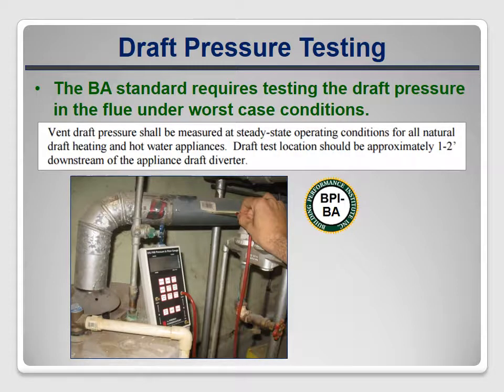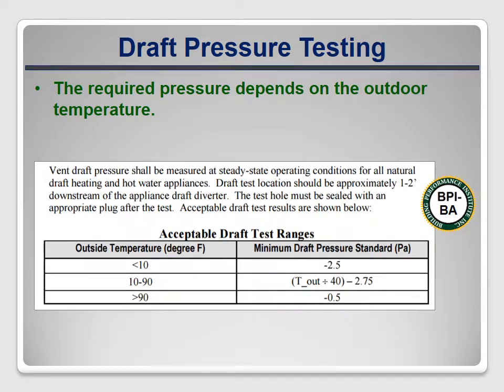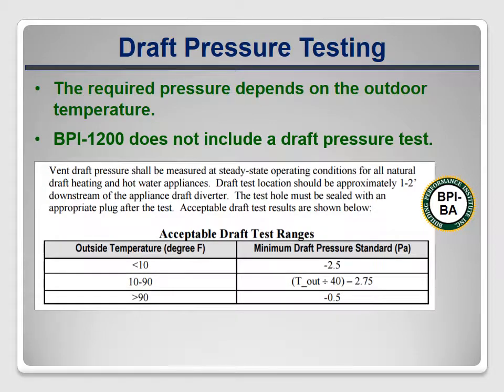The BA Standard requires that the vent draft pressure be measured for all natural draft appliances, specifying the appropriate test location, with the required draft pressure depending on outdoor air temperature at the time of the test using an included equation. BPI 1200 does not include this test, presumably because if an appliance passes the worst-case spillage test, the draft pressure must be acceptable.